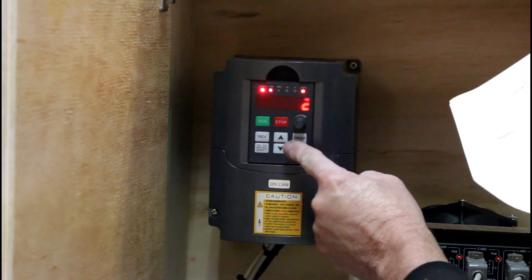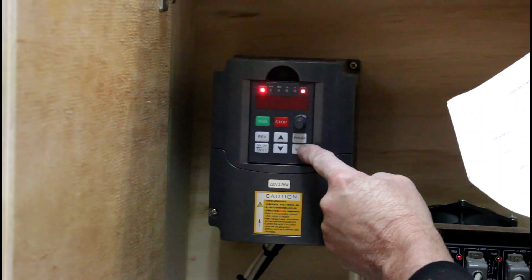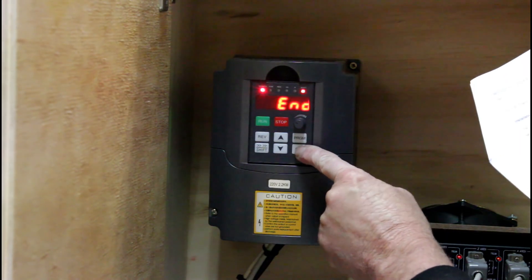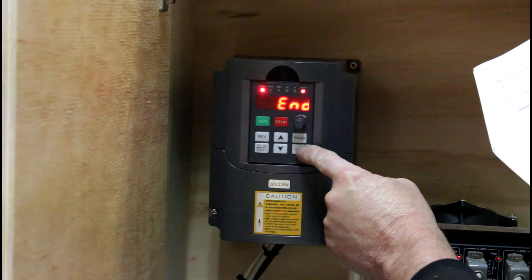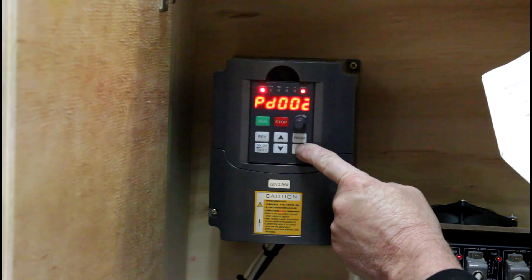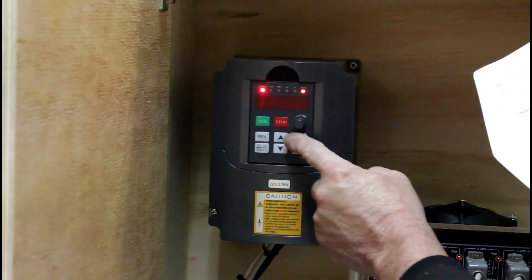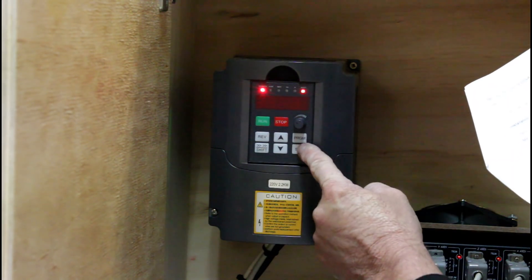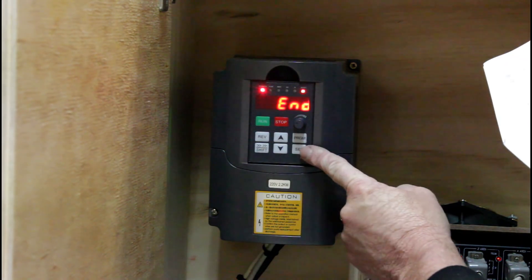Registers 1 and 2 need to be set to a value of 2. This enables commands on the RS485 port of the VFD.